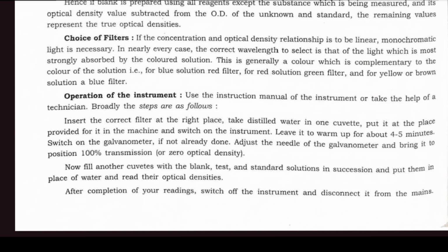Leave it to warm up for about 4 to 5 minutes. Switch on the galvanometer if not already done. Adjust the needle of the galvanometer and bring it to the position of 100% transmission or zero optical density. Now filter or fill another cuvette with a blank test and a standard solution in succession and put them in place of water and read their optical densities.